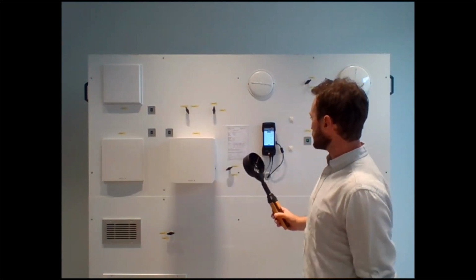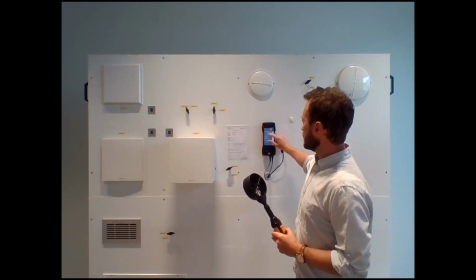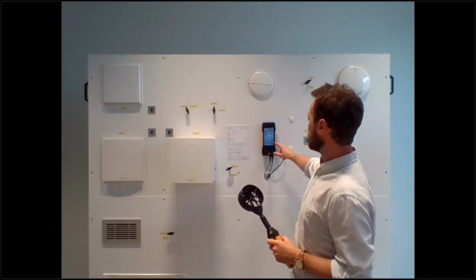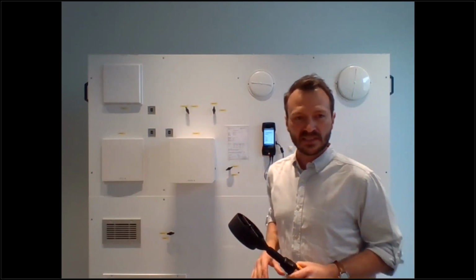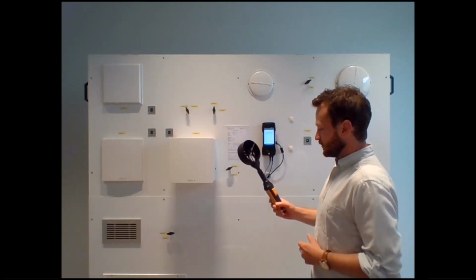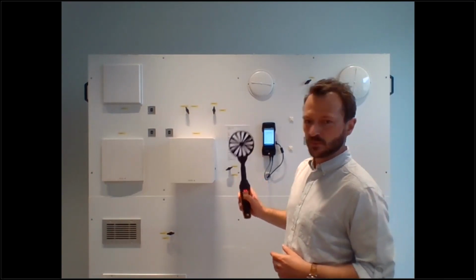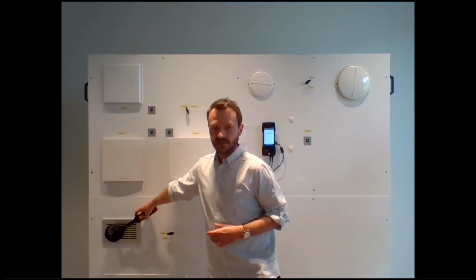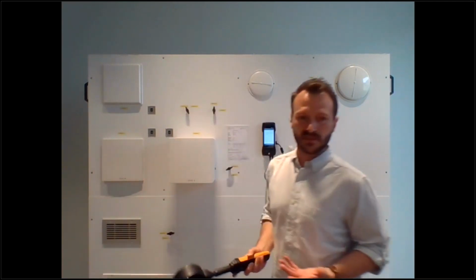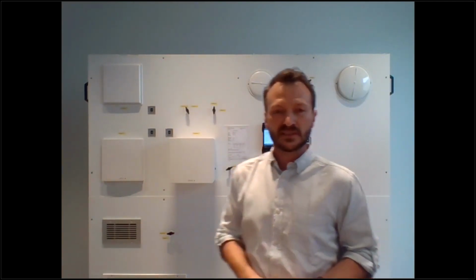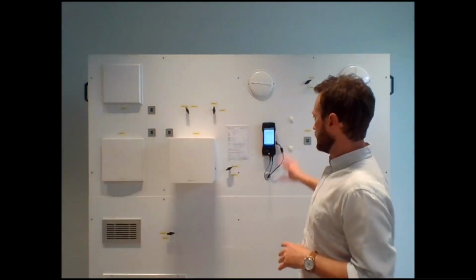Then you can click on the right measurement menu, like funnel or outlet measurement, and enter the customer data with dimensions and so on. Then you go with the 100mm vane probe to the outlet and measure the air velocity, and the instrument calculates the volume flow. You can save it, report it, and send it by email or Bluetooth to your office or directly to the customer, combining it with your invoice, for example. So pretty easy and very flexible usage.